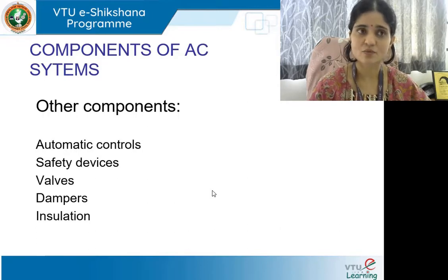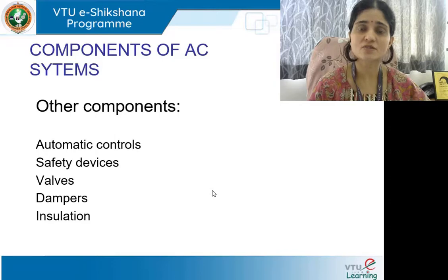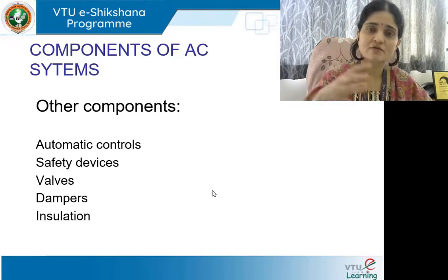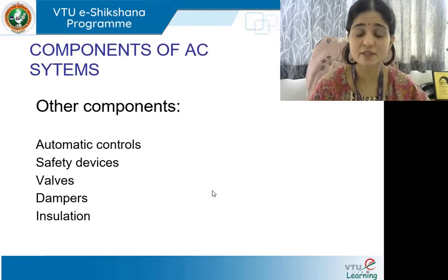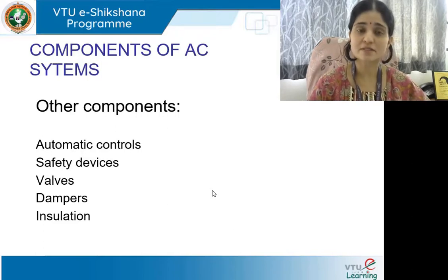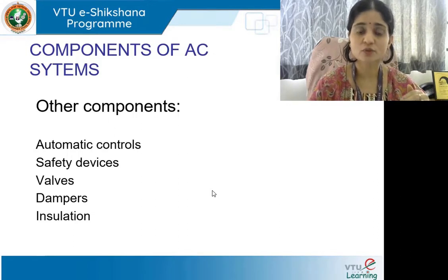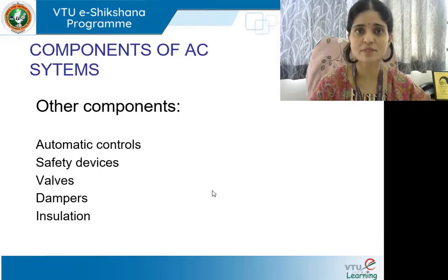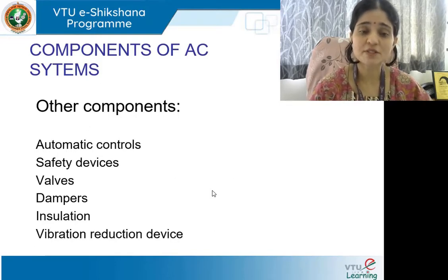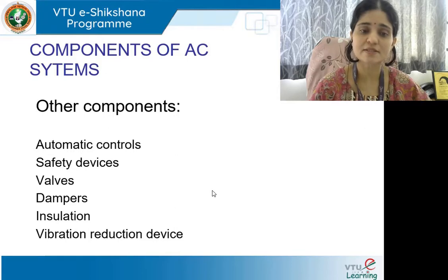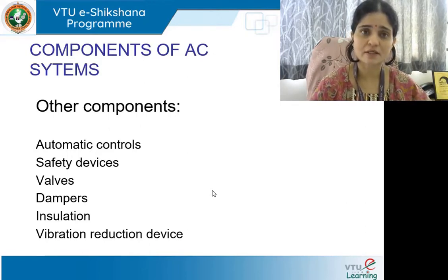Insulation is very important — the conditioned space must be insulated, otherwise the conditioned air will not remain conditioned when infiltrated by outside heat. The ducts running through non-conditioned spaces also need insulation to minimize loss of conditioned air in terms of temperature and humidity. Vibration reduction devices are also necessary, as so much mechanical process happening in the equipment is likely to cause substantial vibration from air flowing through ducts and spaces.